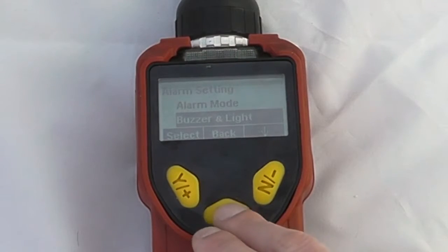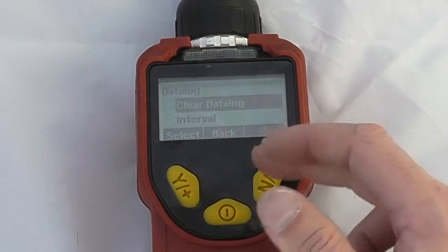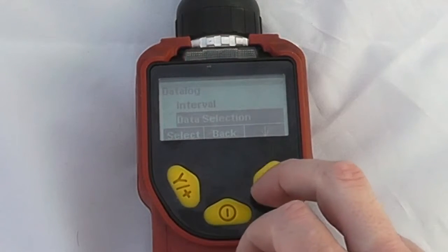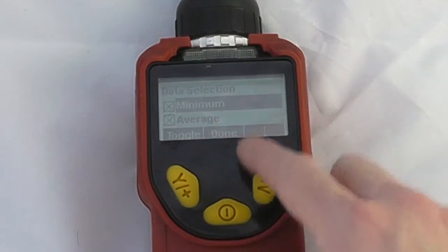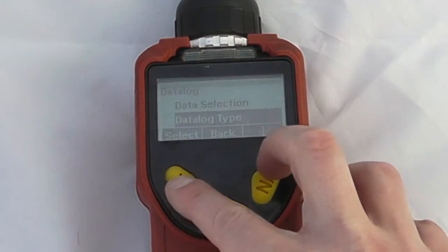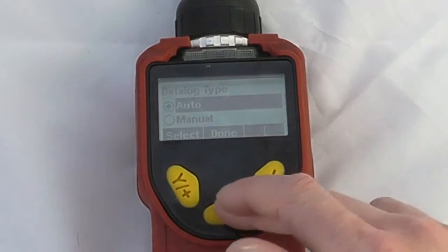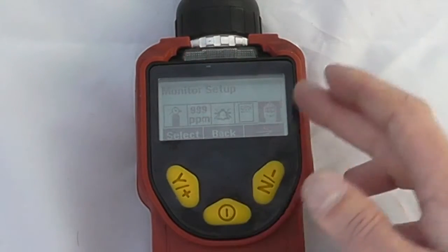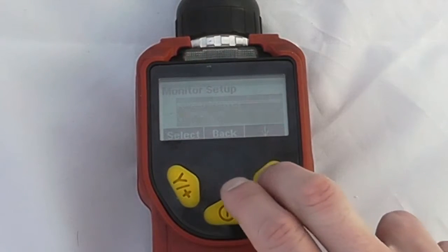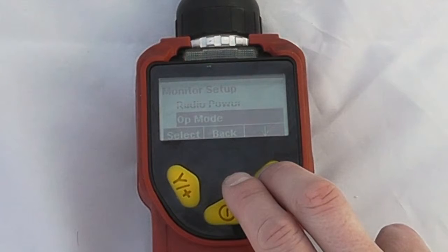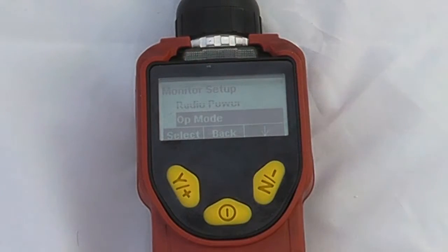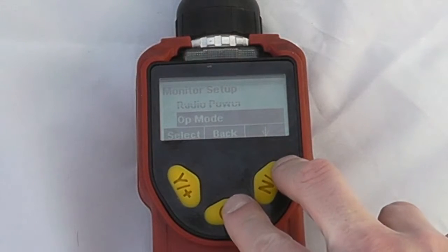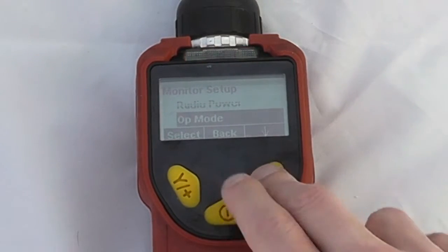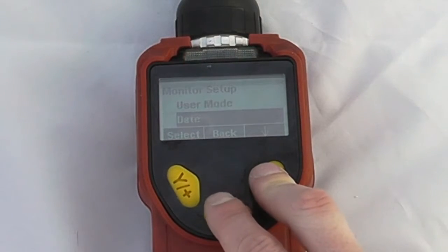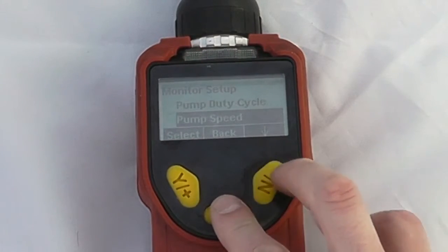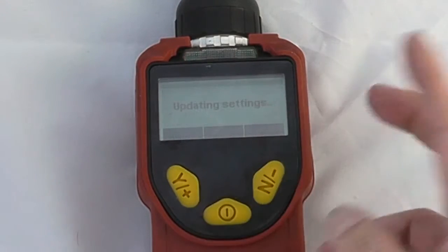In our data log settings, we can look at clearing the data log, any particular intervals we want to look at, the data selection, so what do we want to store, minimum, averages, etc. Our data log type, be it automatic or manual, so automatic would be working from startup. In our general monitor setups, we can see things like radio power, operation mode, etc. Now these will be primarily for calibrating for use with the wireless mesh card system. But we can see things like site ID, user modes, etc. And that's operationally the end of the instrument.